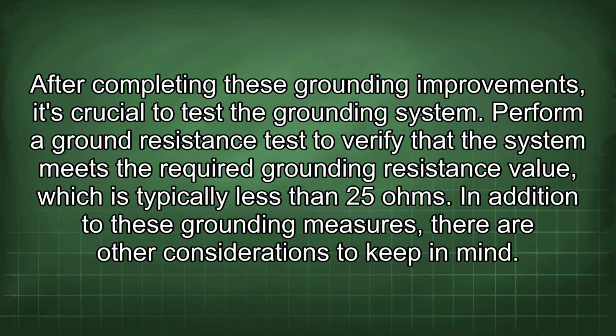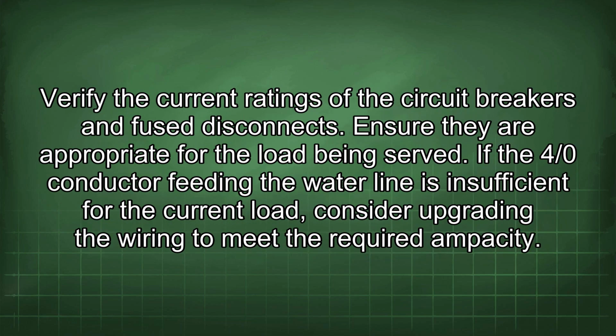After completing these grounding improvements, it's crucial to test the grounding system. Perform a ground resistance test to verify that the system meets the required grounding resistance value, which is typically less than 25 ohms. In addition to these grounding measures, there are other considerations to keep in mind. Verify the current ratings of the circuit breakers and fused disconnects. Ensure they are appropriate for the load being served.